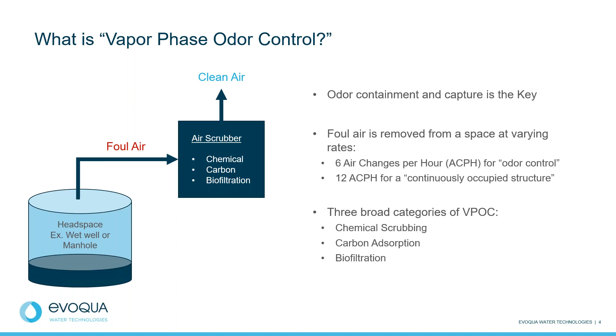The first technology we will be talking about is chemical scrubbers. Chemical scrubbers are a type of air scrubber that use a combination of sodium hydroxide, or caustic solution, and sodium hypochlorite, or bleach, to first dissolve odors and then oxidize those odors so that the air vented from the system would be free of nuisance smells.